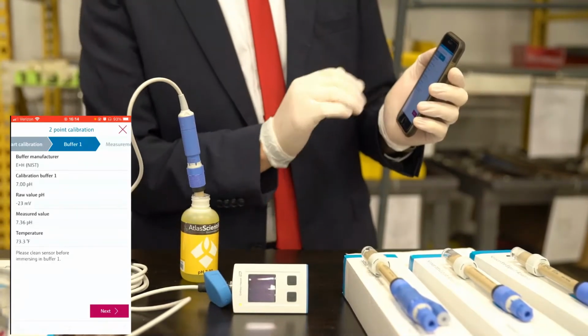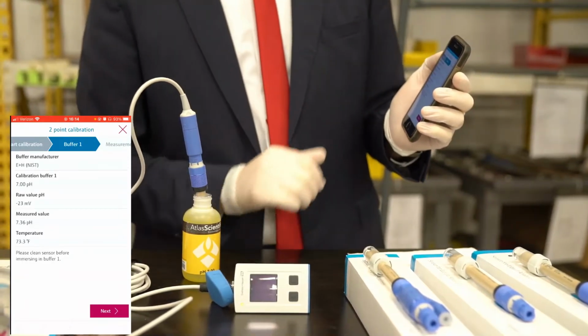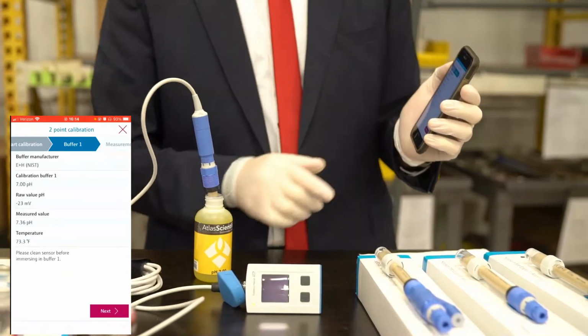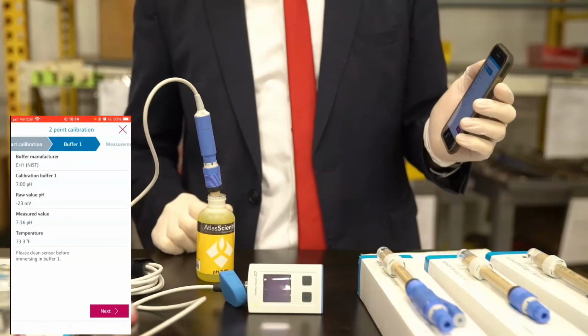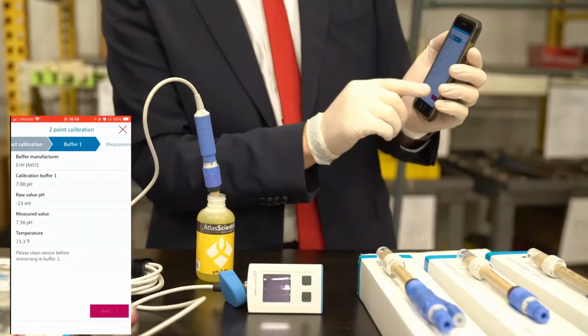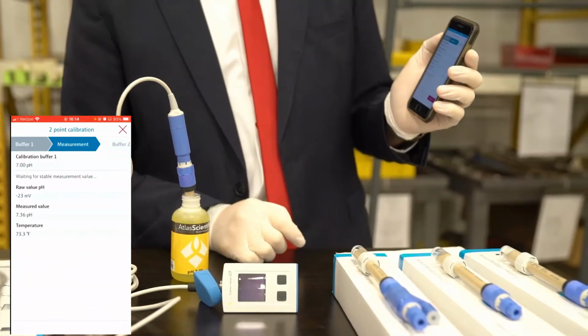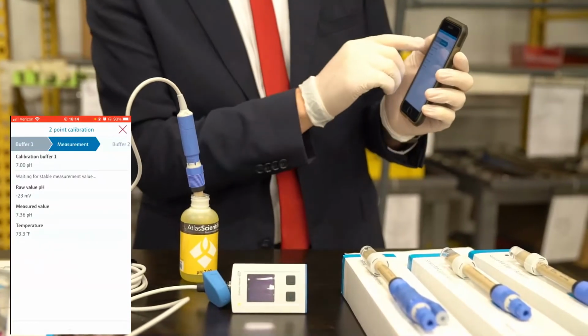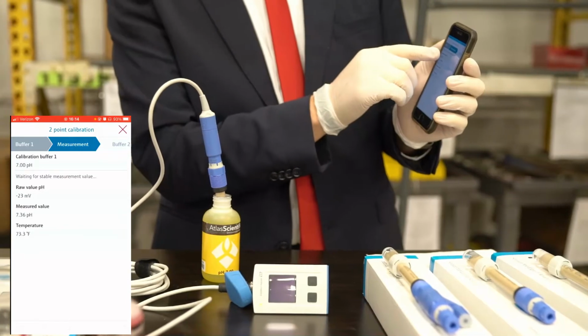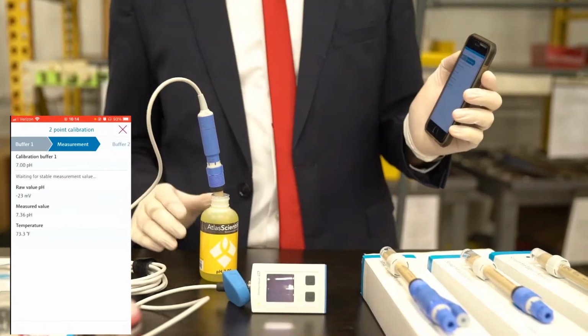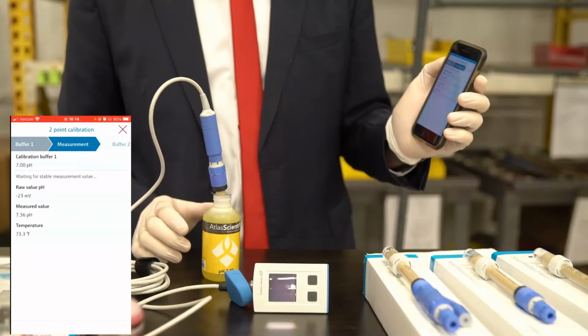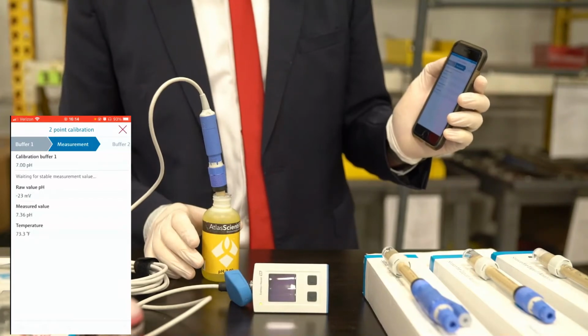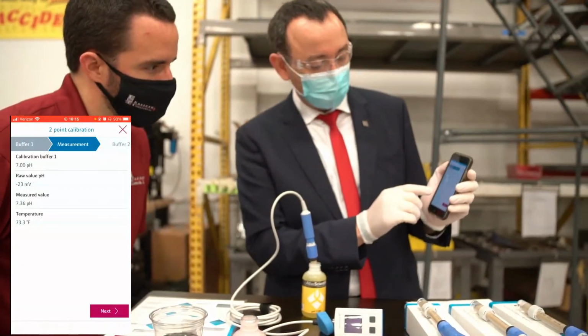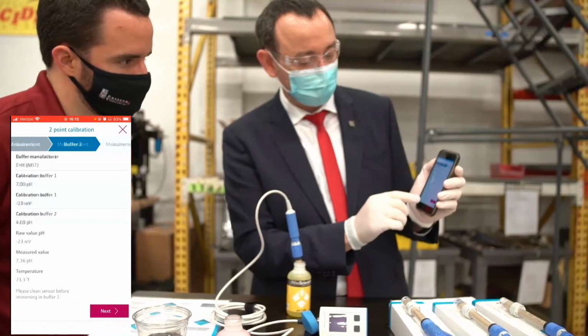The first step is to calibrate in buffer 1, which is pH 7. And we hit next. The transmitter is waiting for a stable measurement. We wait for a while in pH 7. Now the first step is finished. We can hit next.